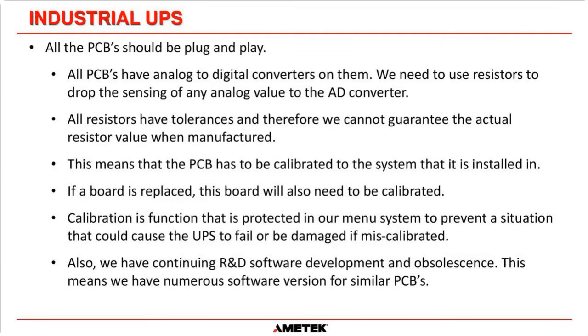So there are some boards that, yeah, you probably could get away with plug and play, but for the majority of our boards, especially the inverter control board, the charger control board, and the static switch control board that is actually monitoring AC and DC values, they're probably going to need to be calibrated. The main control board, the display, yeah, it is pretty much plug and play these days, but all the other boards related to it, unfortunately, are not plug and play.